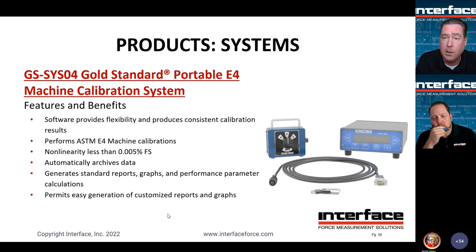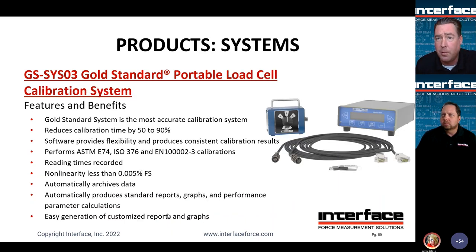It is used as the A to D, and the software is communicating through the PC to the 9840, pulling data off of it, and actually stores all the standard polynomial curve fit data and standard data on the software side, and data is entered through that. Again, this is used for ASTM-E4 machine calibration, with the load cell being sized around form factor and force range requirements. I should also touch on one of the features.